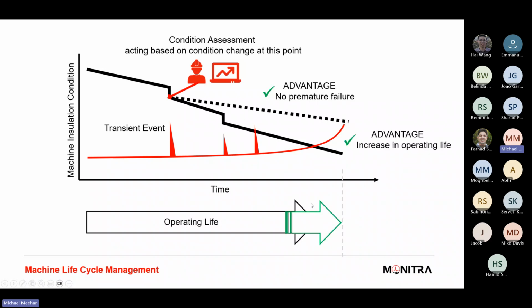So by implementing these systems, we end up with two key advantages. We increase service life, and we reduce the risk of in-service failures, which are costly to both operators and obviously the production process of a particular facility. In a hazardous area facility, a failure of a HV machine could be catastrophic. If you're a power generator, it could be a loss of revenue and significant penalties from any agreements in place in the networks. So the cost of these failures is fairly significant for most operators who have them.